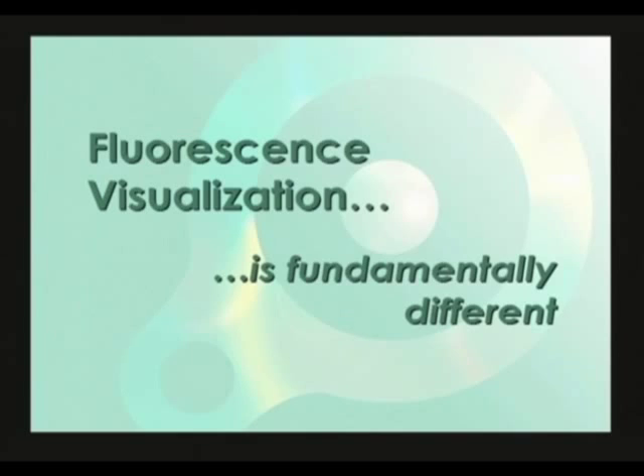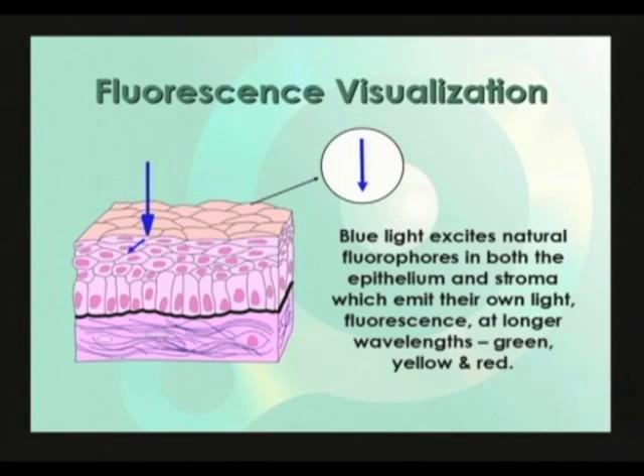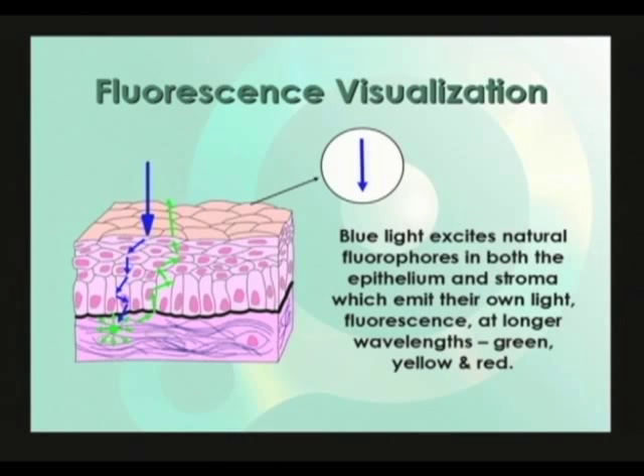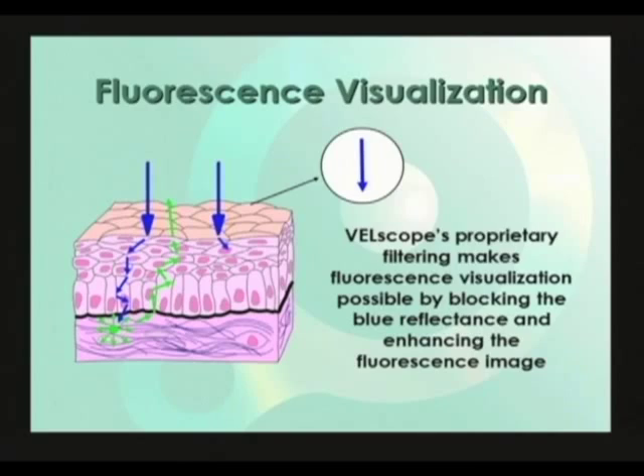Fluorescence visualization is fundamentally different. When we illuminate the tissue with light of an appropriate wavelength, such as blue light, it enters the tissue just as it does for reflectance, but now it can be absorbed by special naturally occurring molecules called fluorophores. These fluorophores absorb the blue excitation light and then re-emit light at a longer wavelength — green, yellow, or red — a fraction of a second later. Blue light excites fluorophores in both the epithelium and the stroma. The natural fluorescence from the tissue is relatively dim, so the VELscope handpiece blocks the much brighter reflected blue light, and proprietary filtering optimizes contrast between normal and abnormal tissue.